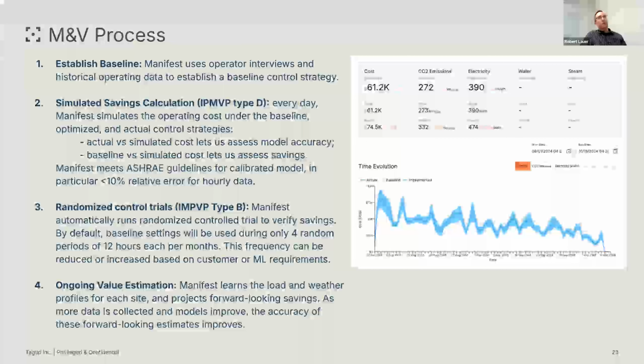What we do as ongoing calculations, called type D in IPMVP jargon, is simulate the operation cost under different scenarios: the baseline that would have been in place had we not installed our system, the optimized way our system will control it, and then what actually happens, since an operator can overrule recommendations or the system may be temporarily disabled.